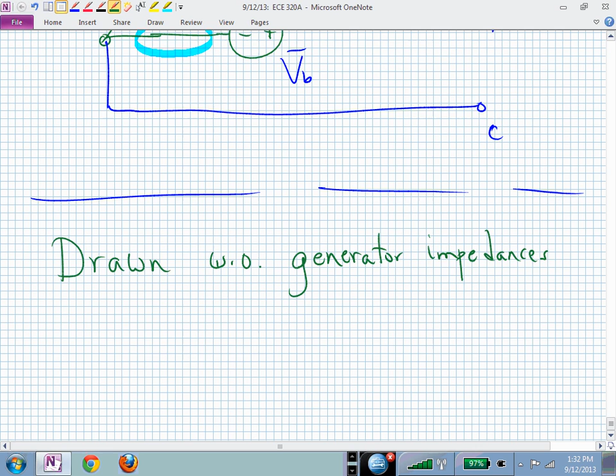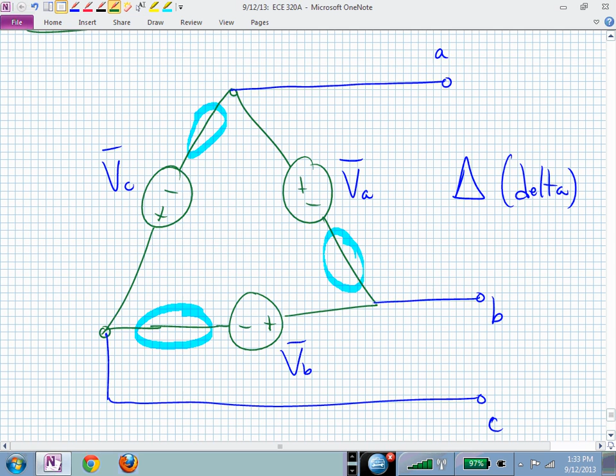So now, where would the neutral line come in this delta configuration? It doesn't exist, does it? You don't have a neutral in this configuration - it doesn't happen, there is no neutral. Good question, it's not there, and it's not there because it can't be there. It's not because I left it off, which is a good reason to ask the question - hey, did you leave something out of that diagram? I can't put it anywhere, right? There's no neutral for those three voltages.